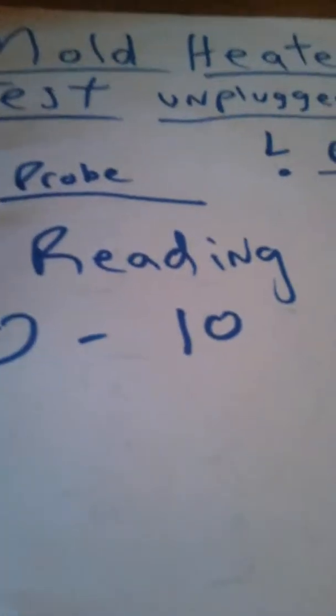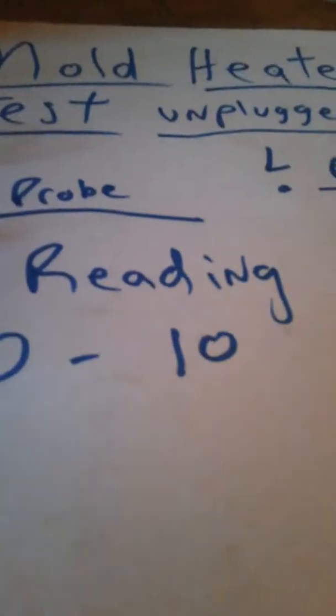Okay, now we are going to the mold heater test. What this does, the heater will melt the ice for just a very short period of time so it will come out of the tray using the motor and dump into your ice bucket. That reading should be between 0 and 10. 0 means there is no resistance. And you say, I don't know what that means.